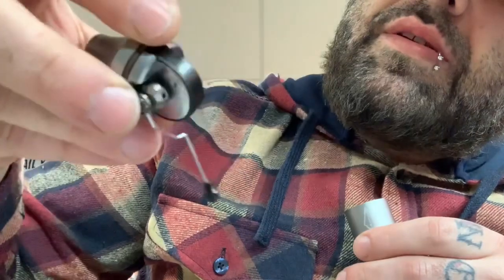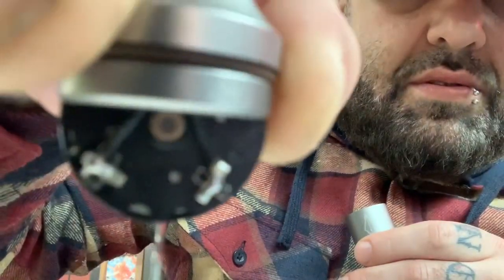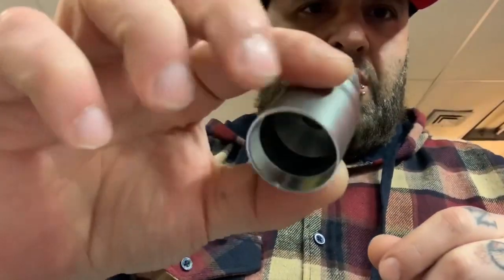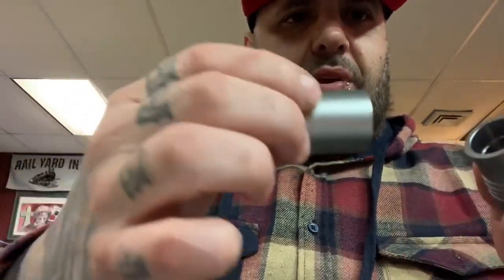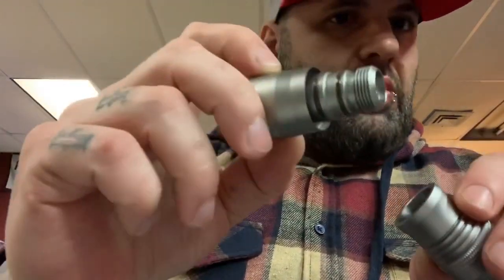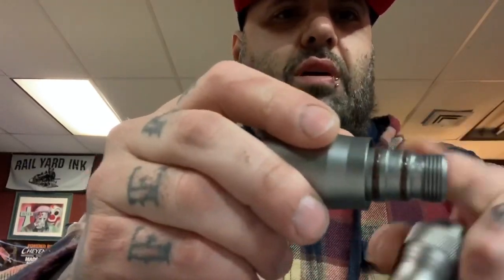It is a Faulhaber motor — it does say Faulhaber. I don't know if you guys could see that; it's not good lighting. But yes, it is a Faulhaber motor. And you can clean this entire body here, which to me is just pretty awesome — that you can fully take this machine apart and just spray it down and let it sit. I'm not sure if you can autoclave this; I have not autoclaved it, and I wouldn't recommend trying to autoclave it, especially with the O-rings on it because those will melt. But it's pretty cool that you can do that with this machine.